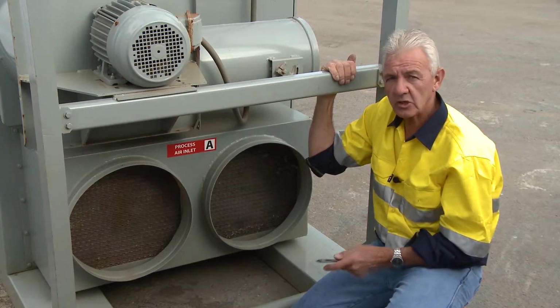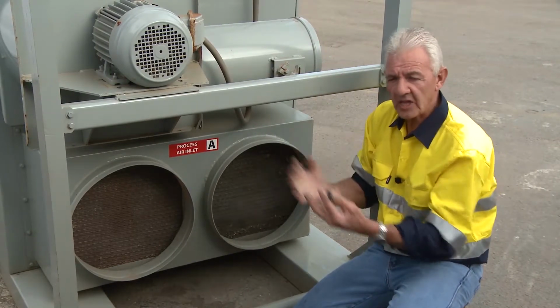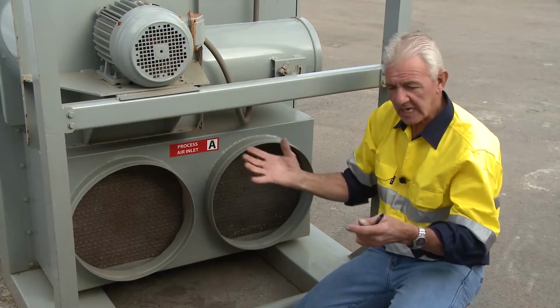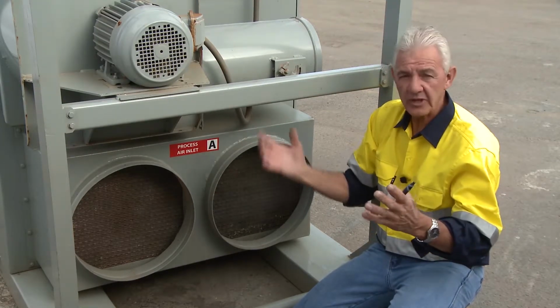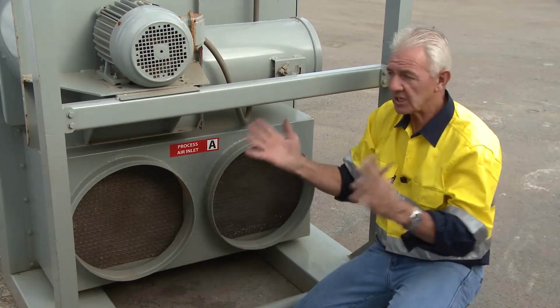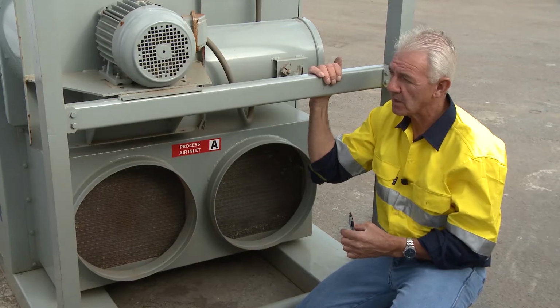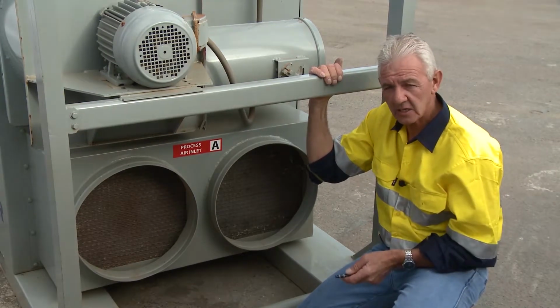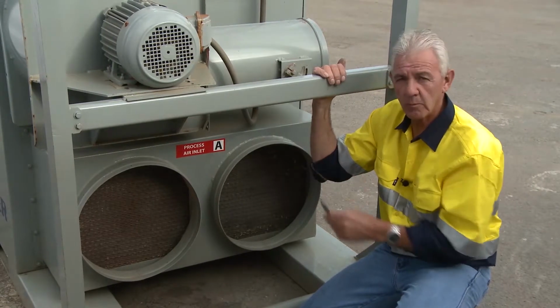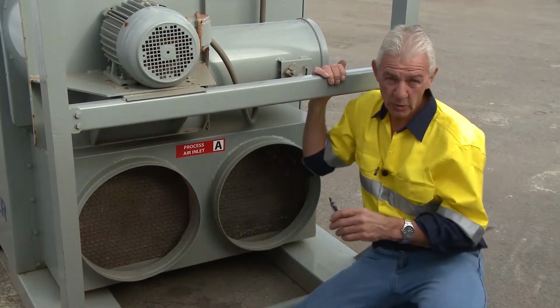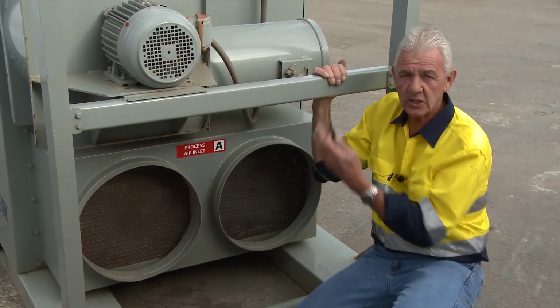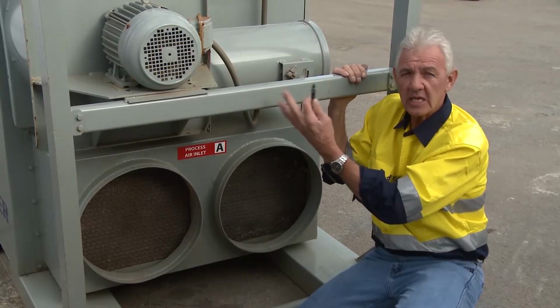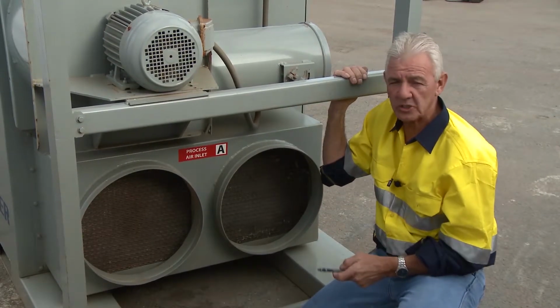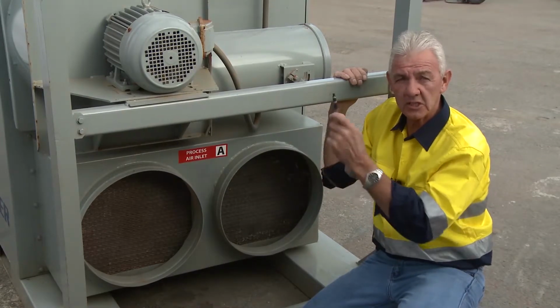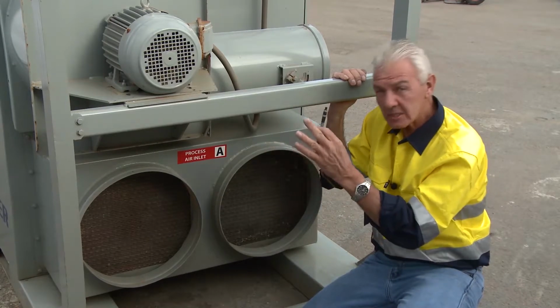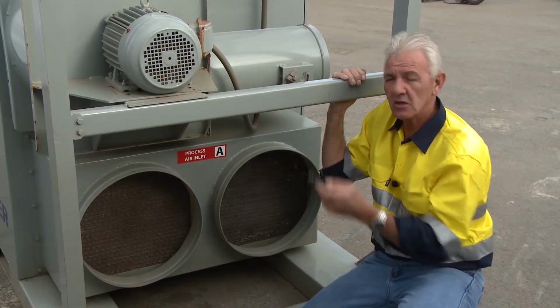So when you first turn this machine on, you'll have one fan spinning that starts up drawing the air in. Now once the air gets to a stage where the machine can read that there's enough volume within the cabinet, the second one will start, and then the machine starts to work in due process. So when the primary motor starts, that's the first one I check, because normally if one of them's wrong, the rest of them will be too. So it's a relatively simple process just to have an electrician change the primary feed. So what I'm saying to you is these are set up and wired to Australian standard. So if it's wrong on site, normally it's the supply power, it's not the machine. So it's the supply power in that they will change that phasing, not on the machine.